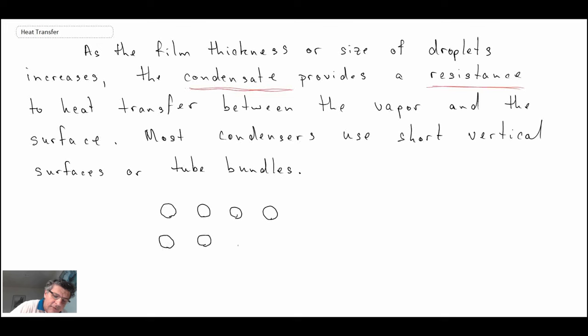This would be where you have what they refer to as shell side condensation, so the condensation is occurring on the outside of the tubes. By having these tube bundles like this, you'll get droplets forming and then the liquid will drip down and go onto the next surface. You're minimizing the overall length that you have in the vertical extent by having a lot of tube bundles like that.